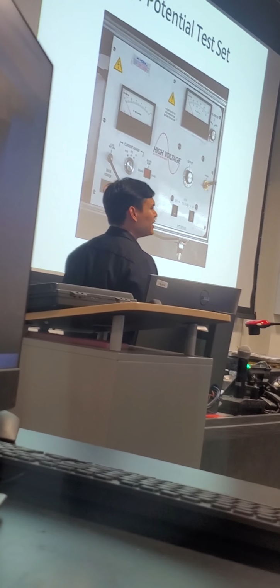You better be sure, just like the Megger has a built-in button you have to press and hold for a few seconds, so you don't trip and fall and zap somebody down the line with 5,000 volts. Same deal here, you can't just turn it on; you have to show specific intent to push tens of thousands of volts. You turn on the main power, you enable the high voltage, and then you crank it up from zero to where you need to go while watching the needle.